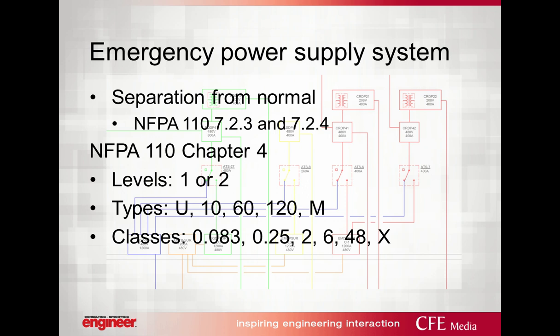But you're going to see levels and classes and types. So level 1 or 2 is very similar to our discussion on loss of life. If somebody could die with the loss of utility power or a system, then level 1 is going to be your selection. It's the most stringent. The type is how long power can be out between the transition from normal utility to the EPSS. So U is uninterruptible, then you have 10 seconds, 60 seconds, or 120 seconds. And lastly, you have manual transfer, meaning it takes as long as you want.